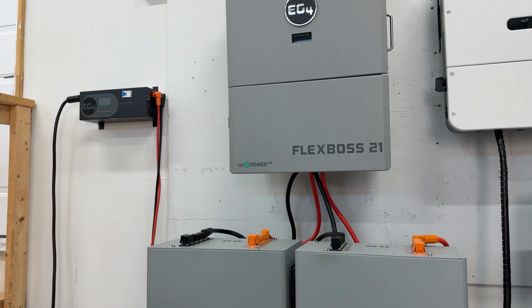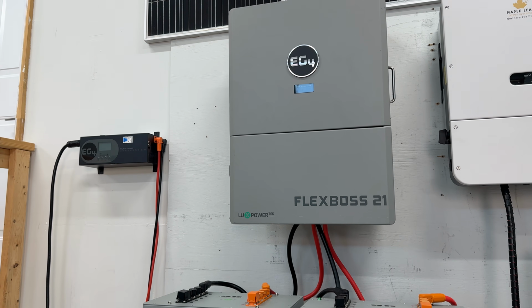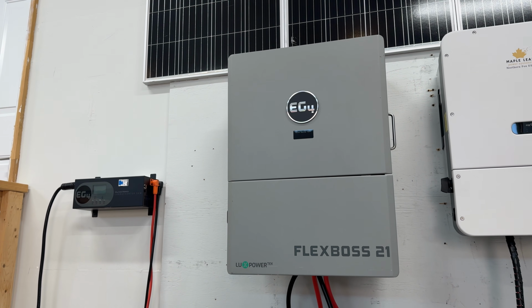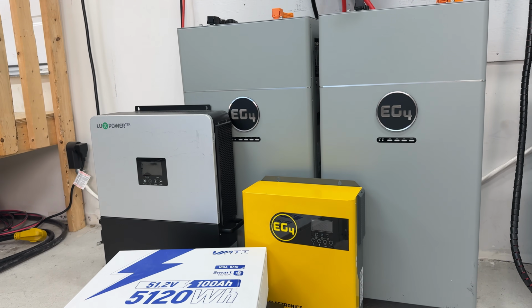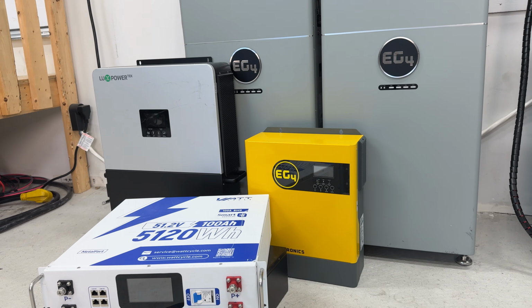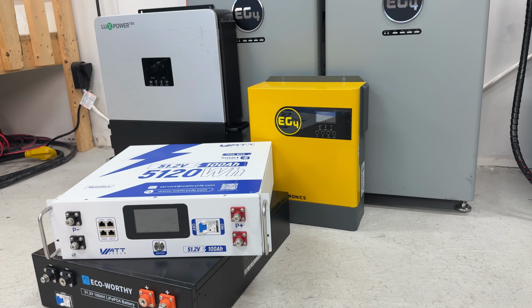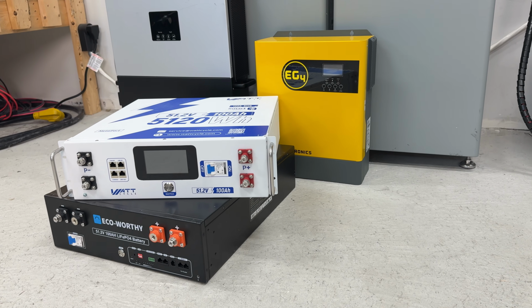Like we said earlier, it's a lot more DIY friendly to do a 48 volt system. One of the biggest reasons is that almost all 48 volt inverters are programmed to have a lead acid mode, meaning it doesn't need to read the state of charge or communicate with your battery at all. It functions based on voltage, which means you could have a 48 volt inverter with any batteries wired together—they could be 12 volts put together to get to 48 volts, or just a bunch of lead acid 48 volt batteries.